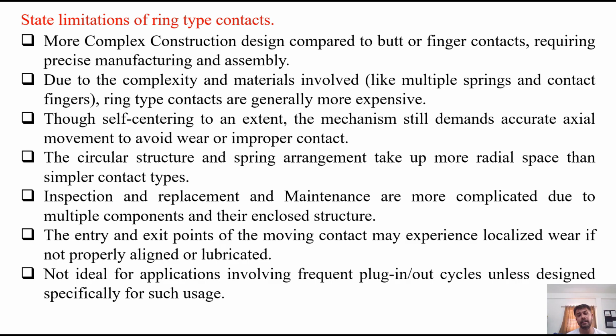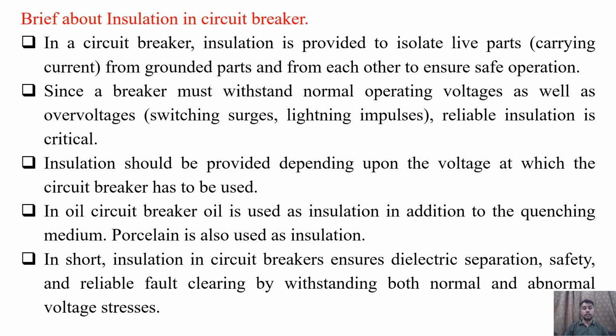Inspection, replacement and maintenance are more complicated due to the multiple contacts and their enclosed structure. The entry and exit points of the moving contact may experience localized wear if not properly aligned or lubricated. It is not ideal for applications involving frequent plug-in or plug-out cycles unless designed specifically for such uses. So these are several disadvantages of ring type contact.